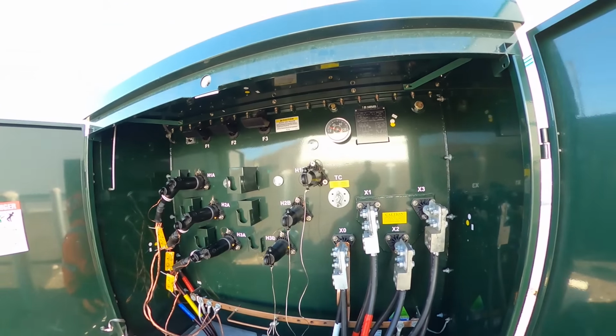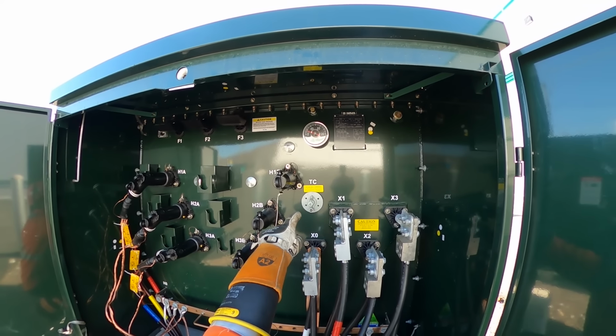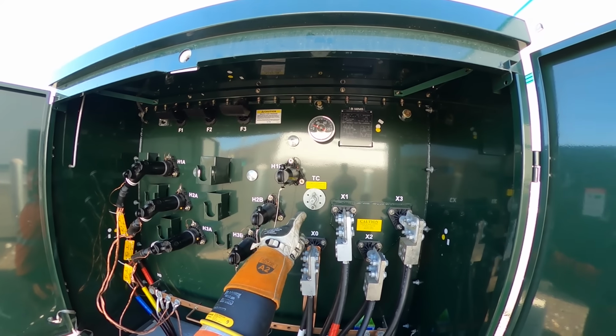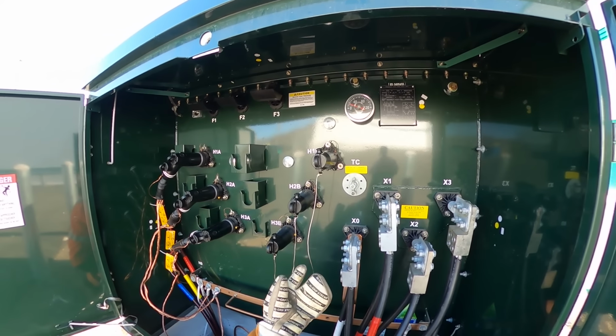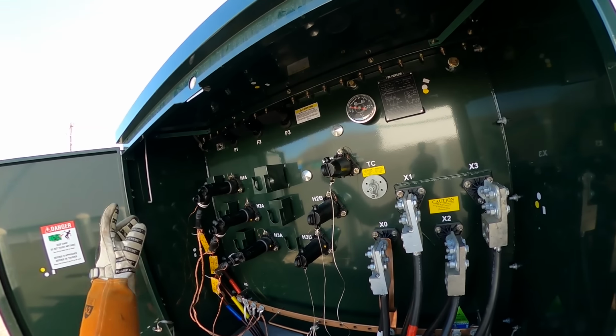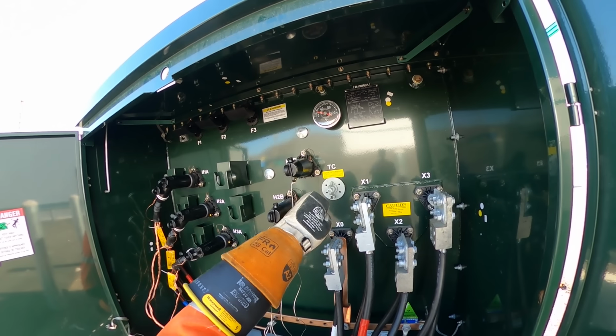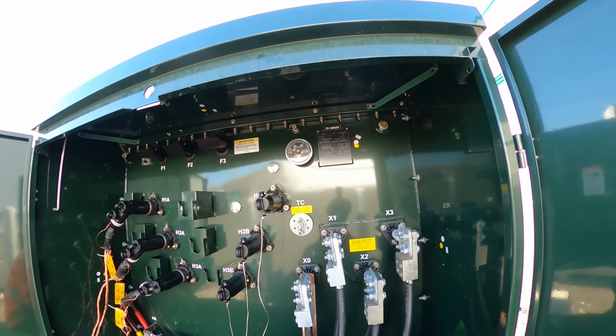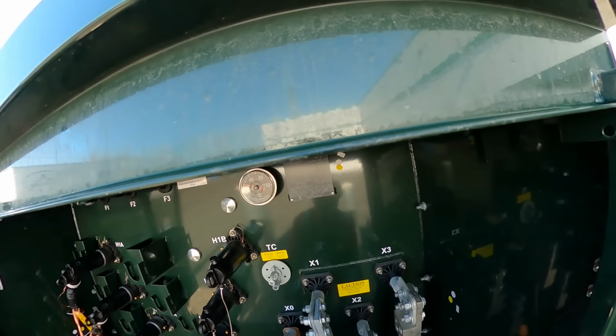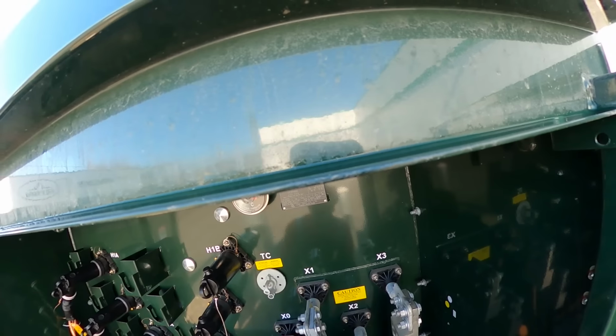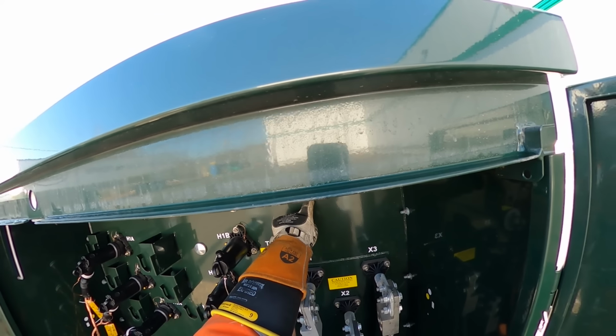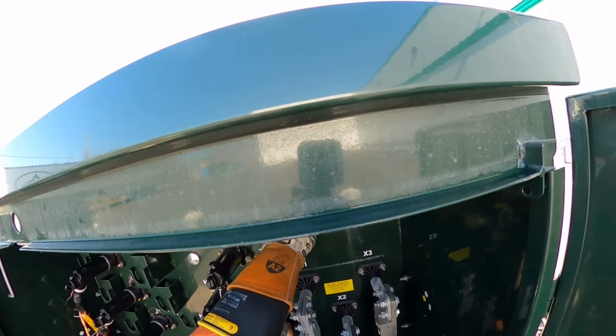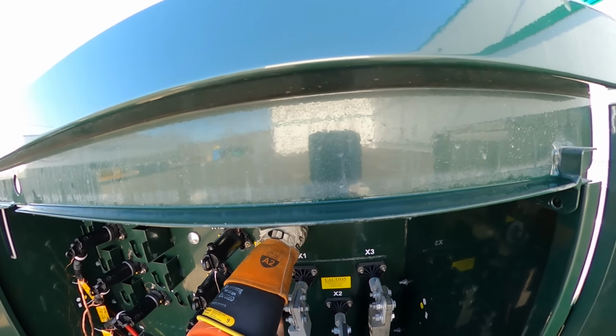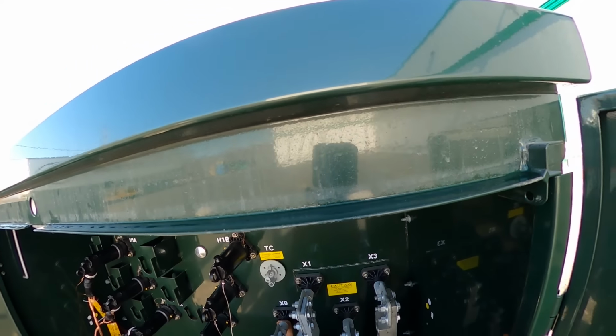If in the end the customer decides the voltage is a little bit high, we do have an off-circuit tap changer here. That can only be operated with the transformer de-energized. Super easy. We just open the switch up, put a screwdriver in there, loosen off that nut, crank that down. That'll bring the voltage down by, I think it's 2.5%, depends on how this is wired up. We can see there, tap 3, it's 100%, so it's basically at the 60-to-1 ratio, and each tap goes up or down by 2.5% on the windings. So we've got a 5% adjustment on voltage if need be.